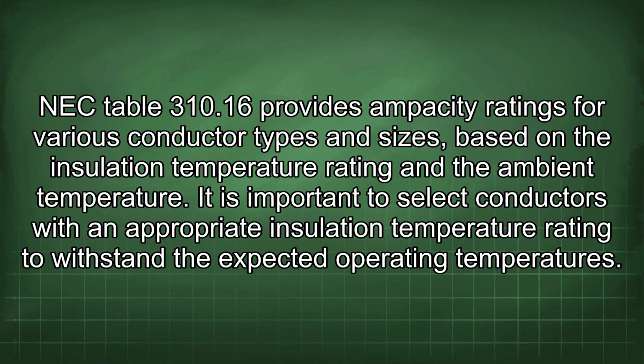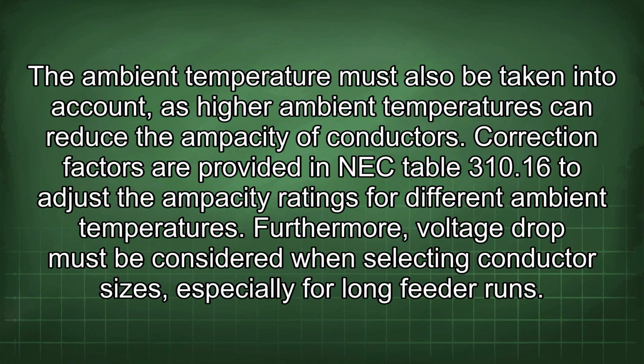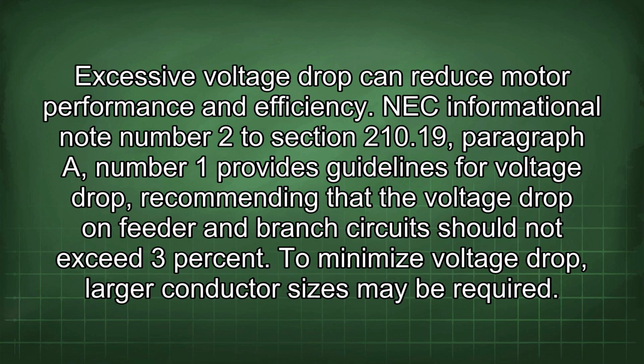NEC Table 310.16 provides ampacity ratings for various conductor types and sizes, based on the insulation temperature rating and the ambient temperature. It is important to select conductors with an appropriate insulation temperature rating to withstand the expected operating temperatures. The ambient temperature must also be taken into account, as higher ambient temperatures can reduce the ampacity of conductors. Correction factors are provided in NEC Table 310.16 to adjust the ampacity ratings for different ambient temperatures. Furthermore, voltage drop must be considered when selecting conductor sizes, especially for long feeder runs. Excessive voltage drop can reduce motor performance and efficiency.